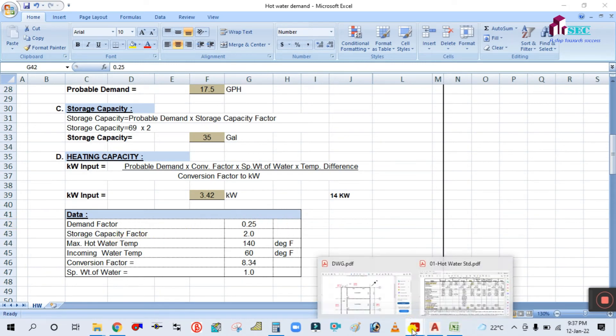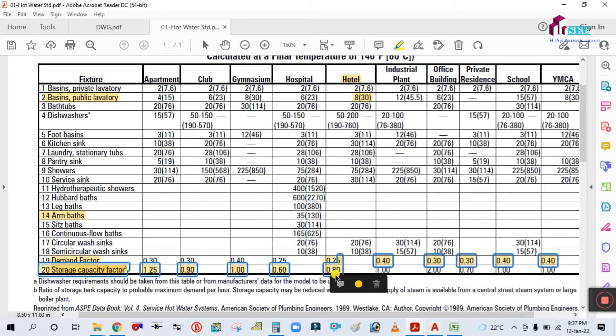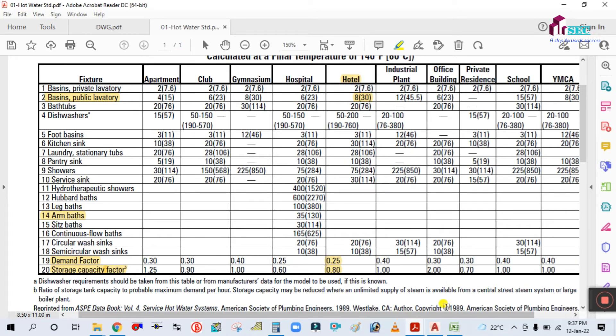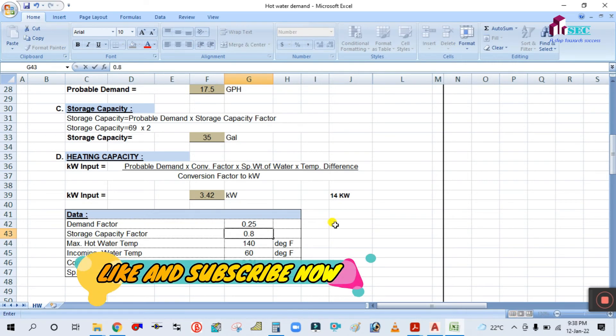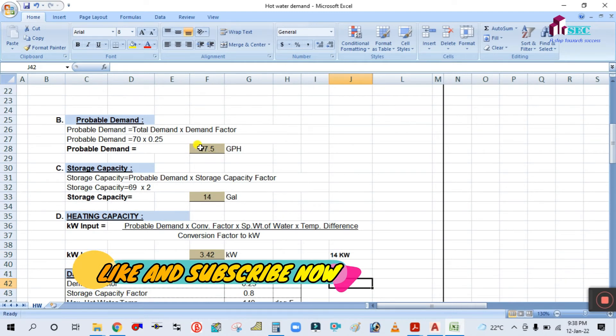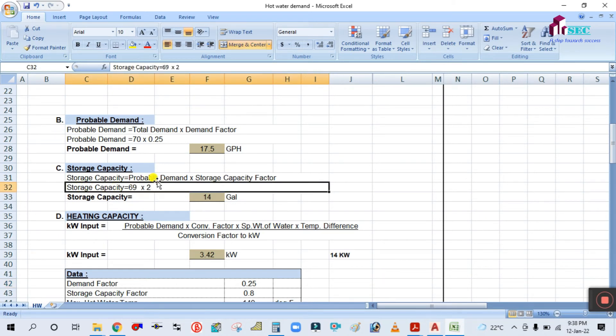Storage capacity factor: you can see here in the table, the storage capacity factor is 0.8 for hotel. Simply enter the storage capacity factor as 0.8. Probable demand is 17.5 GPH. Storage capacity is nothing but probable demand multiplied by the storage capacity factor: 17.5 × 0.8.